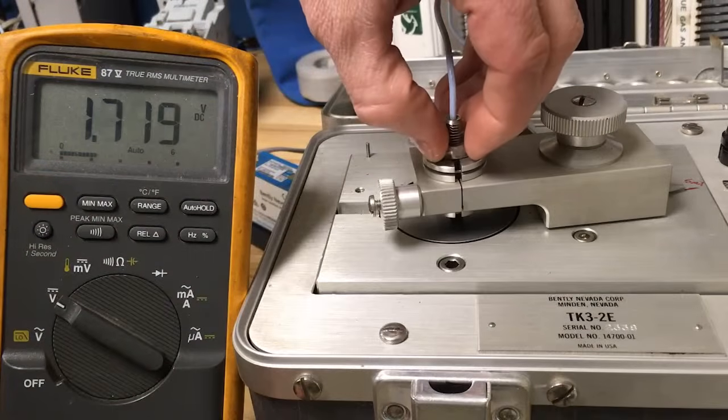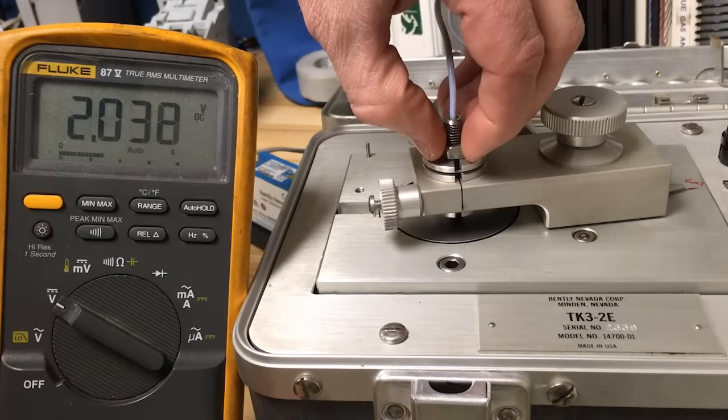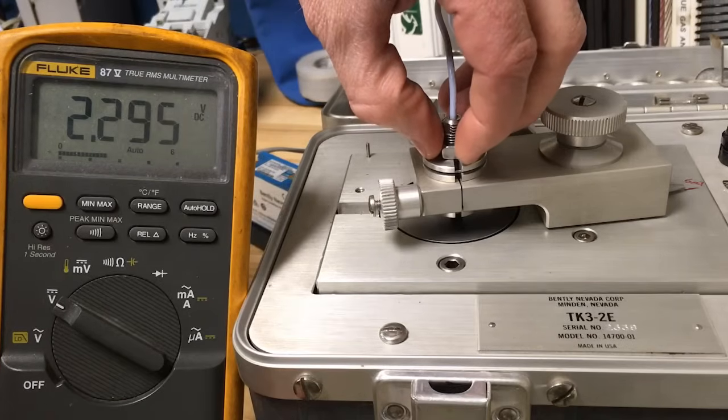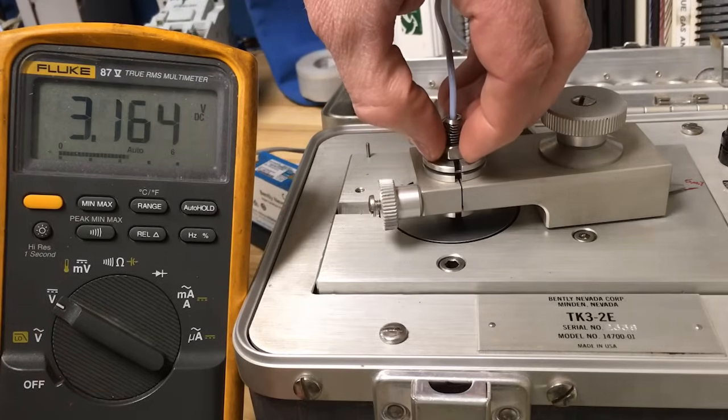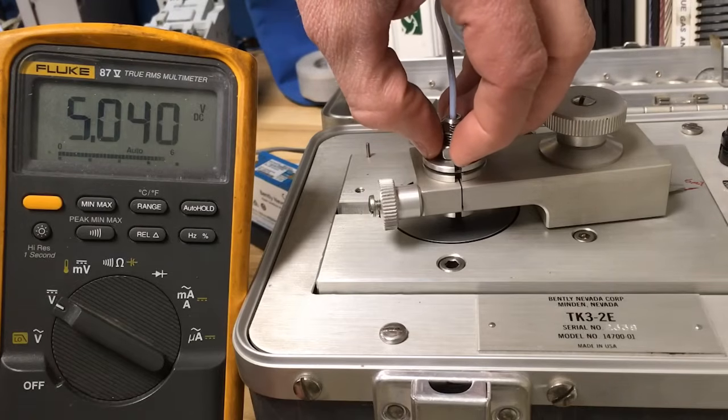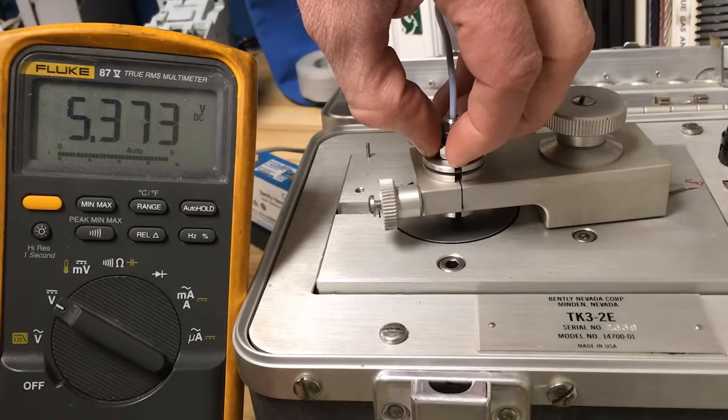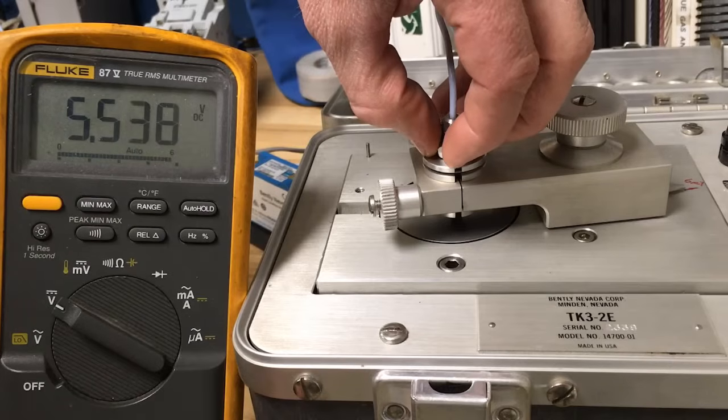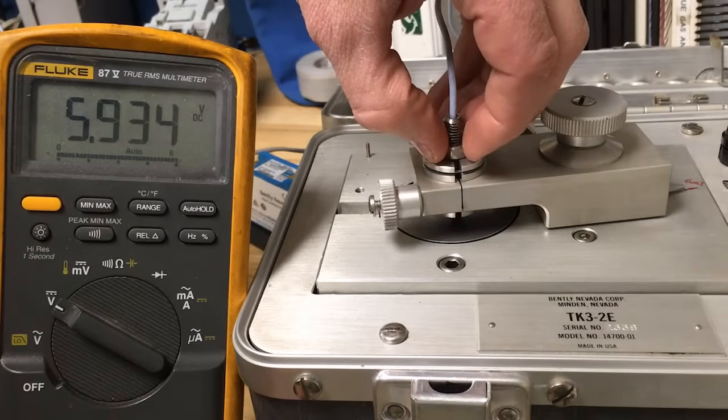Secure the probe in place with the finger screw of the swing arm. Monitor the voltmeter while you use the jam nut to pull the tip of the probe away from the surface of the disc. Continue pulling the probe away from the surface until the previously calculated gap voltage value is measured on the multimeter. In this case, it will be approximately 6.5 volts.